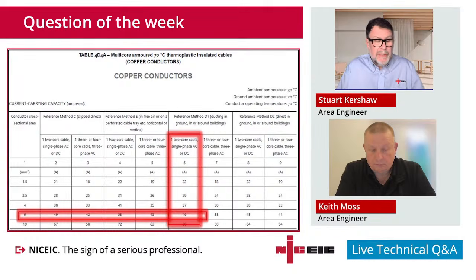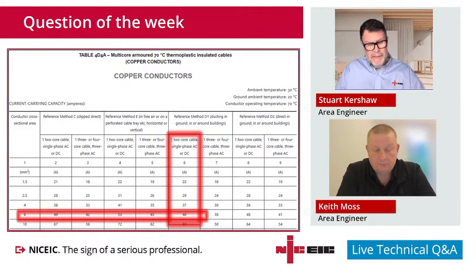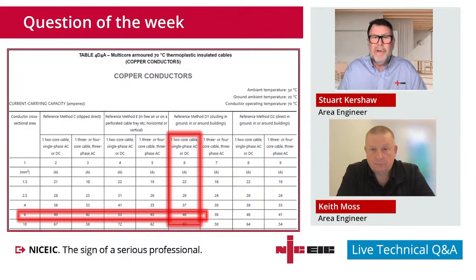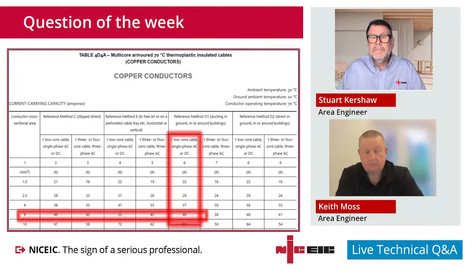Which has then triggered the change in the table, 4D4A. We've now got two columns for single phase and three phase of those reference methods D1 and D2 mirrored in there. So looking at column 6 for the 6mm cable, referring to thermoplastic, you look across and it's 46 amps.